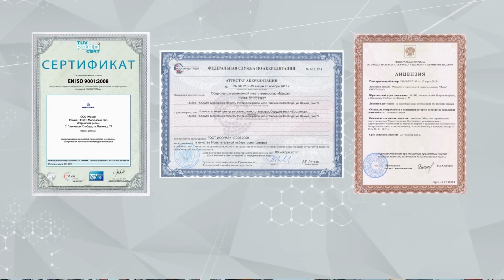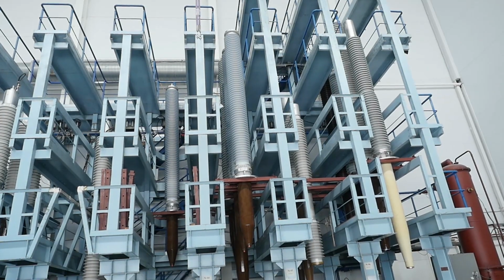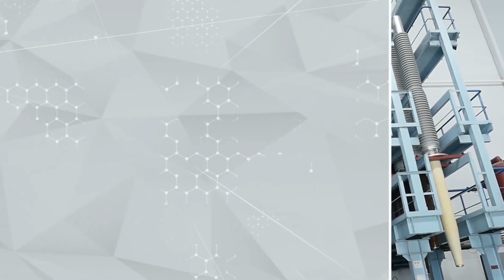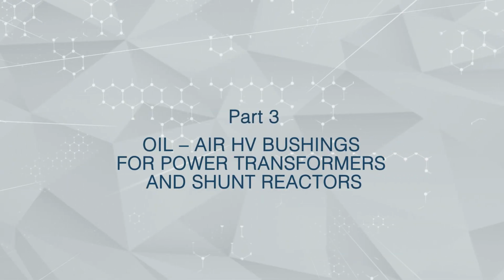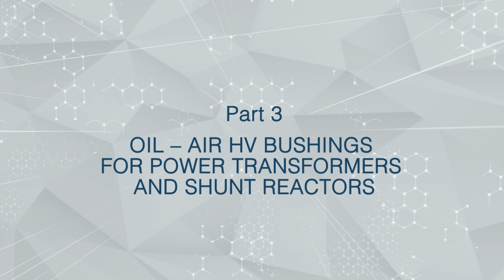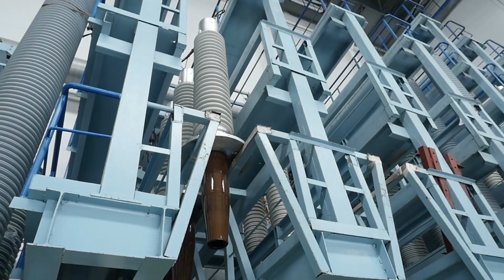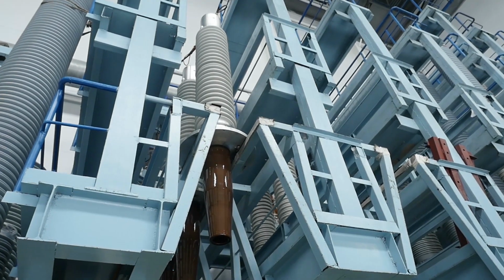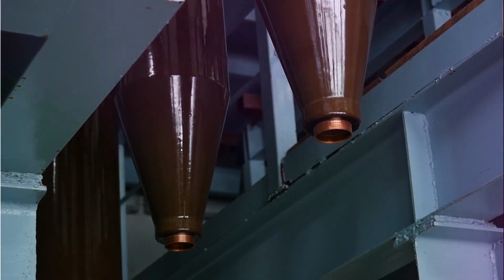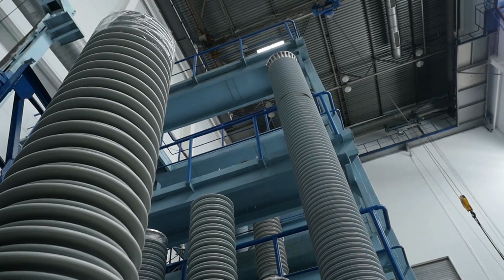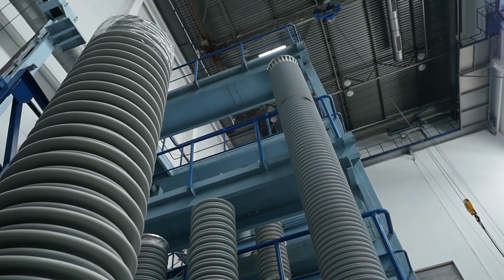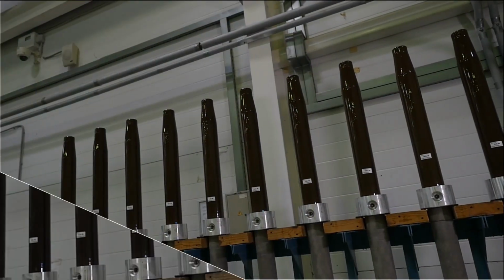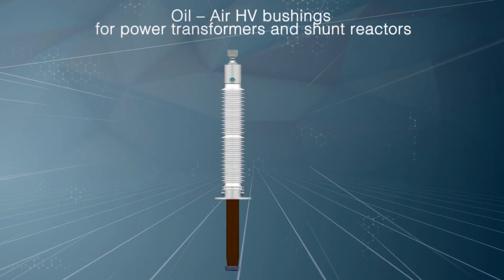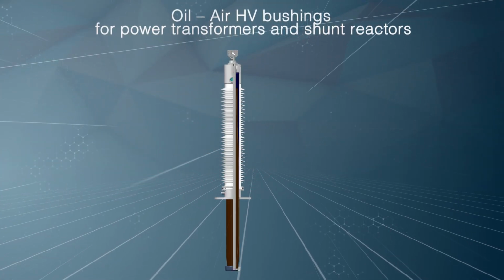Let us consider the design of several high-voltage bushings produced by Izolyator. Oil to air, high-voltage bushings for power transformers and shunt reactors. On the engineering side, bushings are feed-through insulators intended for leading in or out high voltage from a transformer or reactor tank and are independent items of equipment. The contact terminal, made of copper alloy, is used for connection of high voltage.